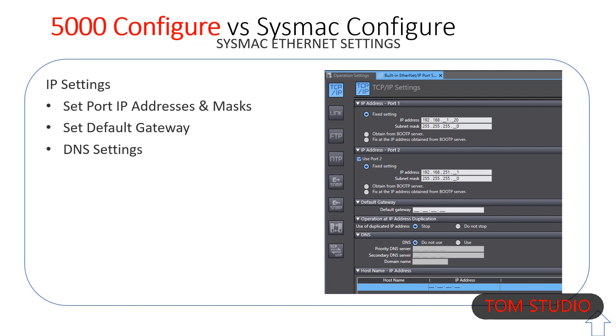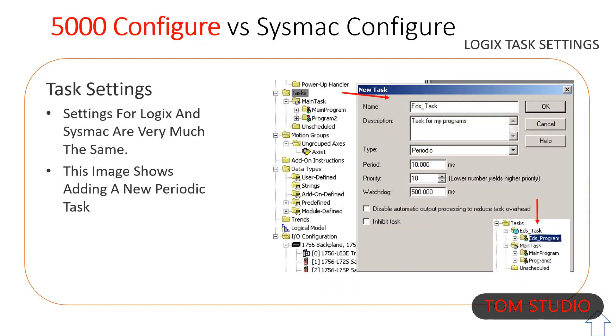In Sysmac Studio, tasks are added to the folder tree. Tasks can be periodic or event-based, can have priority assigned, and can have tags and parameters assigned. Tasks also have a disable option for automatic control of outputs. New programs are added under the task folder.